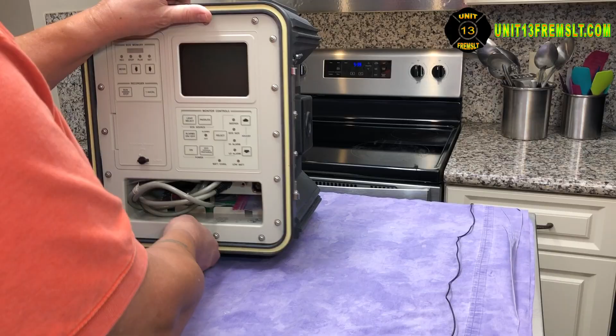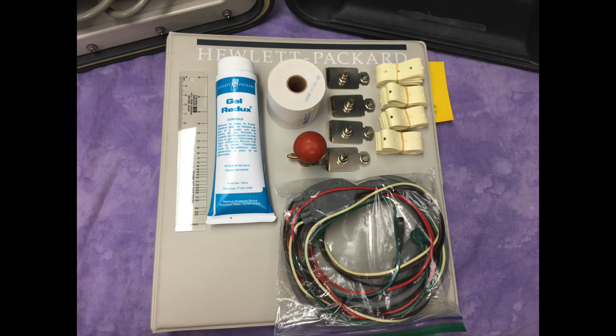I'm going to put up on the screen here so you can see what the unit comes with. It comes with the operations and service manual, thermal tape, the thermal recorder tape, strap electrodes, suction cup or Welsh electrodes, the electrode gel, and then also the patient cable. It's a 5-lead unit, and you can see here that it seals really well, so much so that it's got a pressure relief valve over here on the side. So if it creates a suction on it, you can get this thing open.